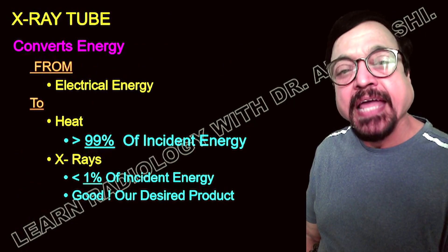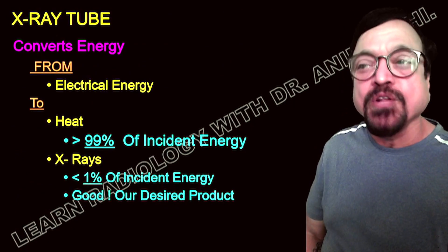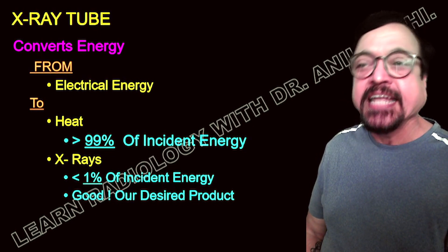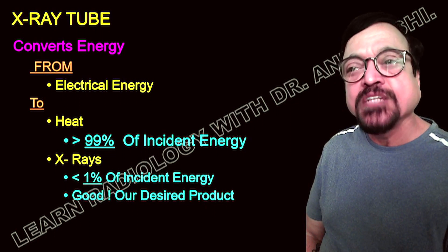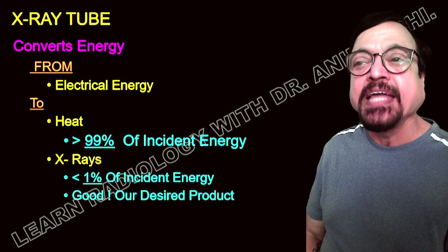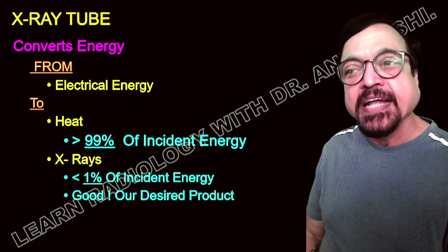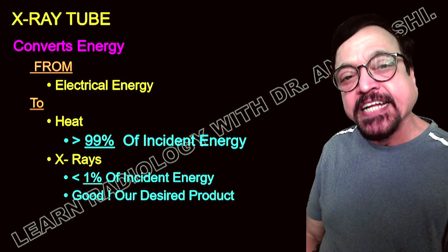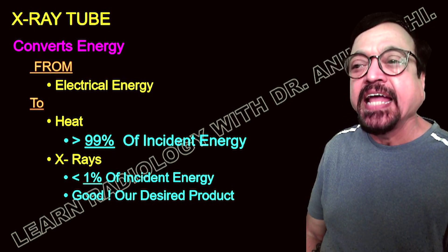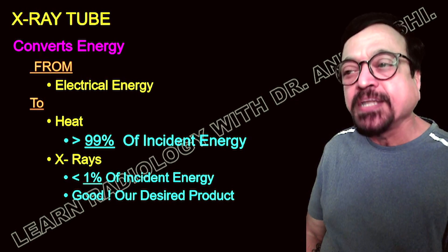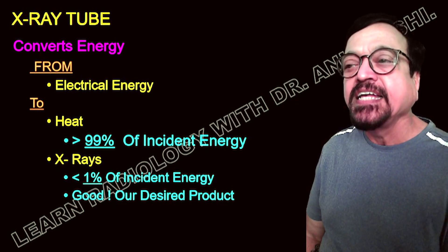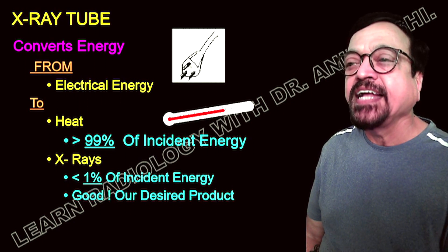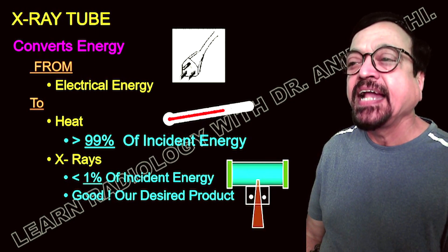The aim or function of the tube is to convert electric energy into x-ray energy. It has incoming electricity coming in, and gives out x-rays. Almost 99% of the incident energy is converted into heat and only 1% is converted into x-rays. The supply is three-phase.